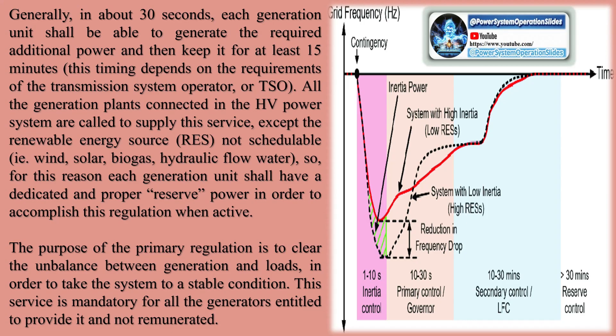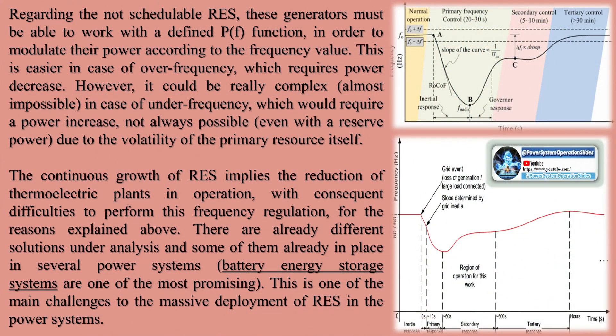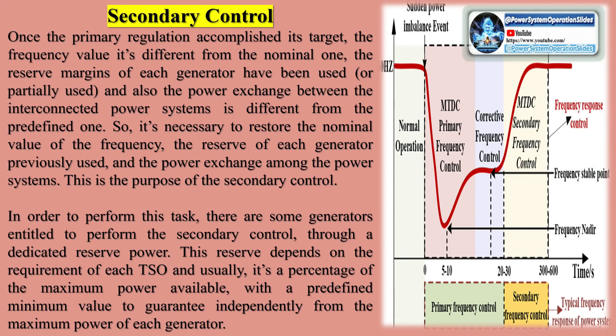When an imbalance between generation and load occurs, the frequency of the power system changes. For example, with a load increase, the generated power doesn't immediately change, so the energy to compensate for this load increase arrives from the kinetic energy of the rotating generators that start decreasing the velocity — this is called the inertial response. After this moment, the speed controller called the governor of each generator acts to increase the generation power in order to recover this speed decrease and try to clear the imbalance. Generally, in about 30 seconds, each generation unit shall be able to generate the required additional power and then keep it for at least 15 minutes. This timing depends on the requirements of the transmission system operator, or TSO.